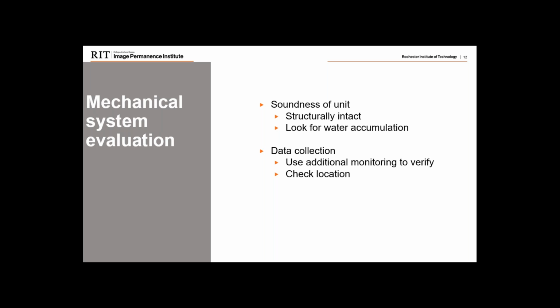We've seen that a number of times, where a door gets propped open on a unit and the air handling unit is just pulling in air from wherever. That will negate any of the work already performed by the unit and wind up giving lower or higher relative humidity downstream because of that. Do you have water inside a unit? It's something we've seen quite a bit. Standing water in an air handling unit can be common, because if a unit is dehumidifying, you're going to have some condensation in there. However, we've seen anywhere from 2, 3, 4 inches of water stuck in a unit. The drain gets plugged, it's just not leaving.